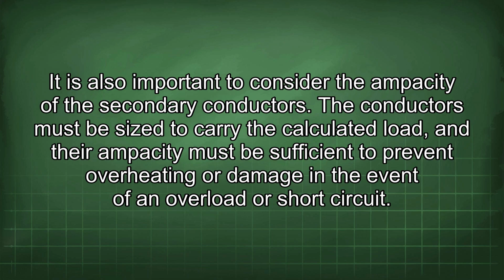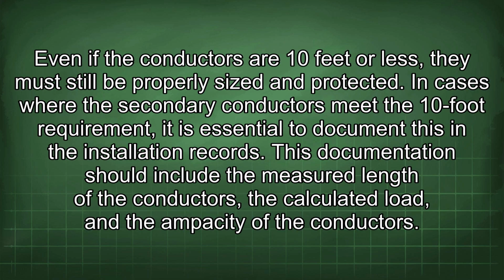The conductors must be sized to carry the calculated load, and their ampacity must be sufficient to prevent overheating or damage in the event of an overload or short circuit. Even if the conductors are 10 feet or less, they must still be properly sized and protected. In cases where the secondary conductors meet the 10-foot requirement, it is essential to document this in the installation records.